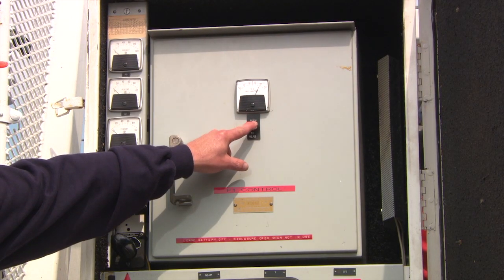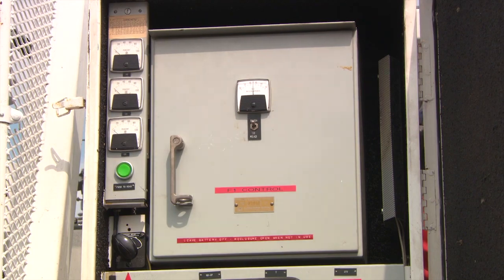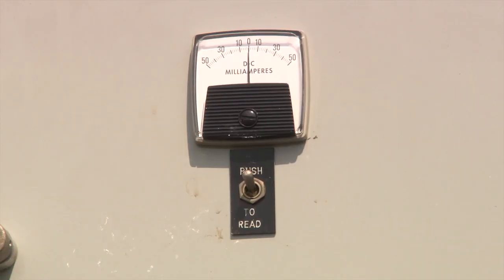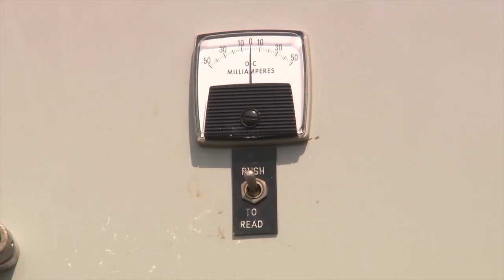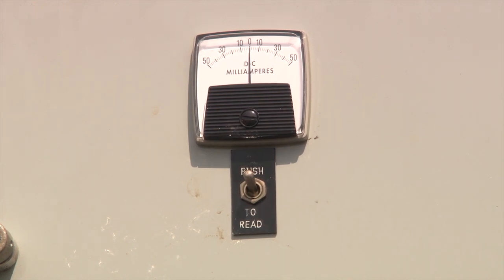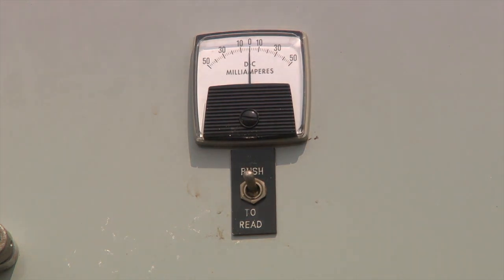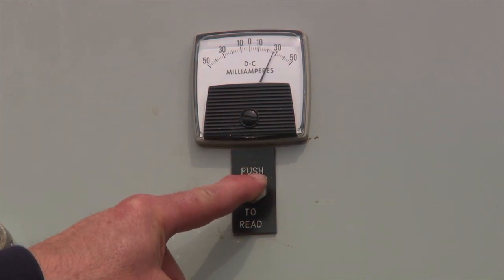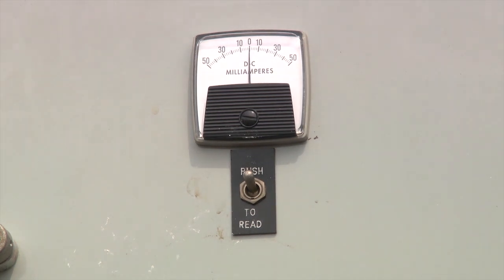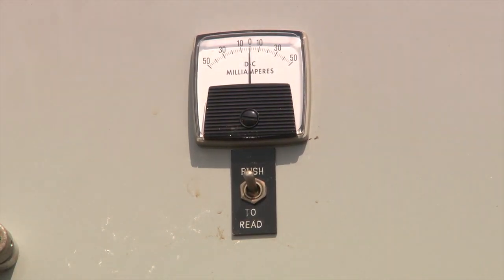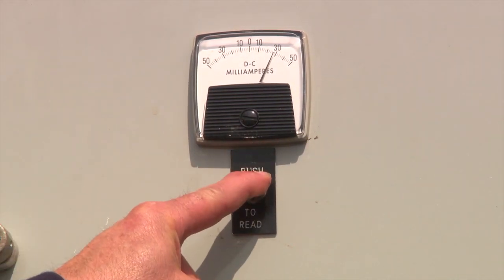Check the battery charging rate in both F1 and F2 recloser cabinets using the recloser battery charger ammeter located on the face of the control cabinet. Press the switch and take a reading. The ampere reading should be between 9 and 30 milliamps. If it's less than 9 milliamps, the battery charger board is not supplying sufficient charging current to the battery, and the board must be replaced.